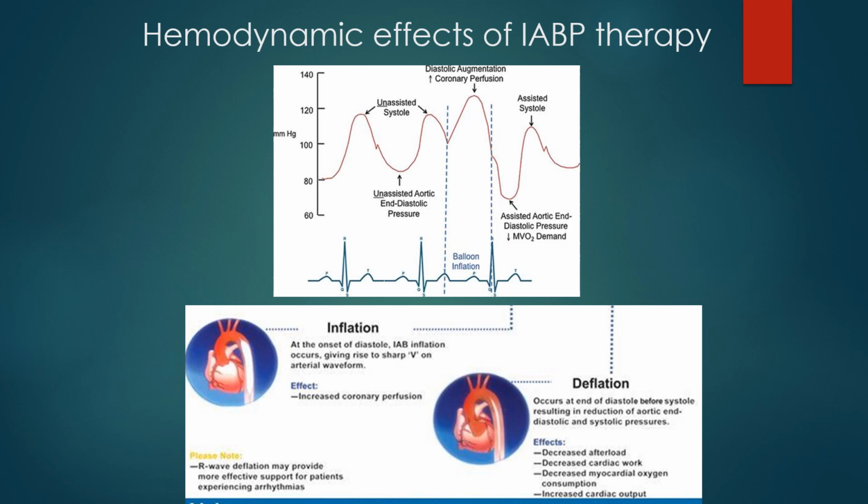So let's take a look real quick at the balloon pump in itself. Let's start with this bottom slide here. Here we have the heart and the balloon. This is the balloon, and it's going to sit right below that aortic arch, about 3 centimeters down. It's going to go all the way down.